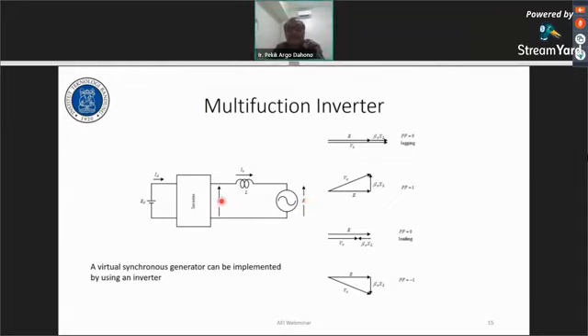If the output voltage is in phase with the grid voltage, and we control the magnitude so that the inverter voltage is higher than the grid, the inverter will generate reactive power. If we control it the other way, the inverter will absorb reactive power. From the utility's point of view, if operated like this, the inverter will be seen as a capacitor; in this case, as an inductor.